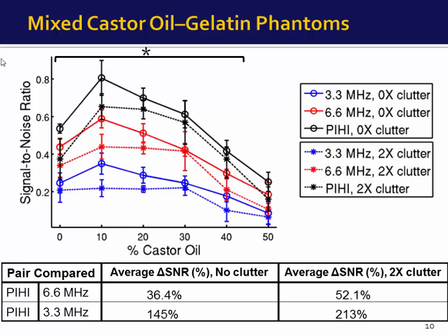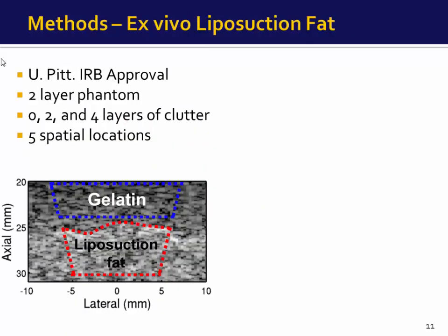With the introduction of clutter, shown in the black dotted lines, there was a degradation in SNR for all tracking modes. However, the relative degradation was smallest for pulse inversion tracking, and as a result the SNR advantage grew to 52.1 percent over 6.6 MHz and 213 percent over 3.3 MHz.